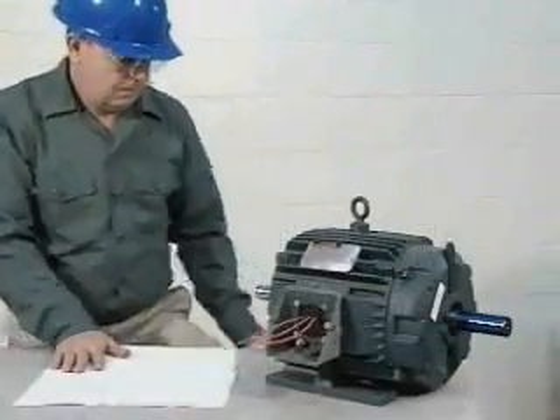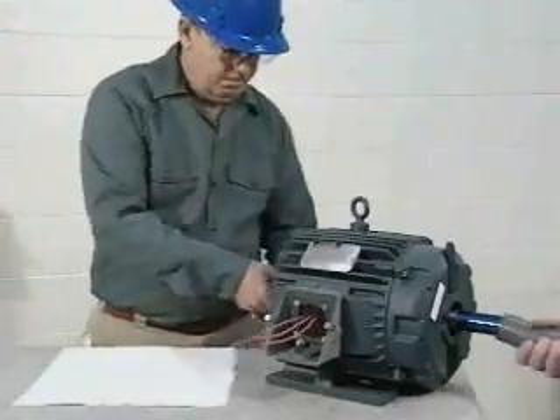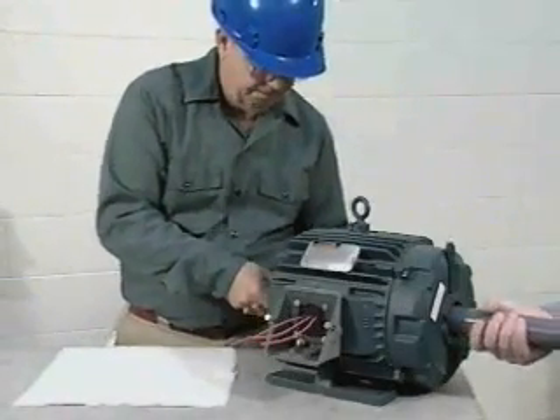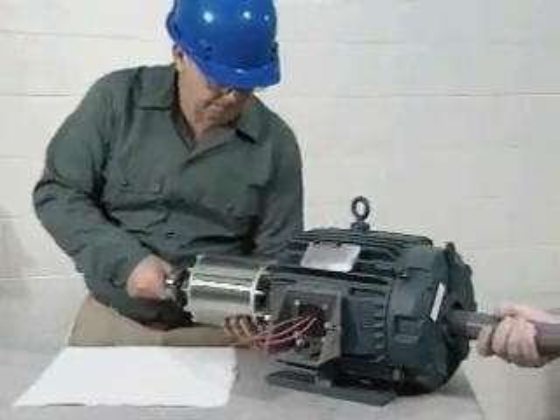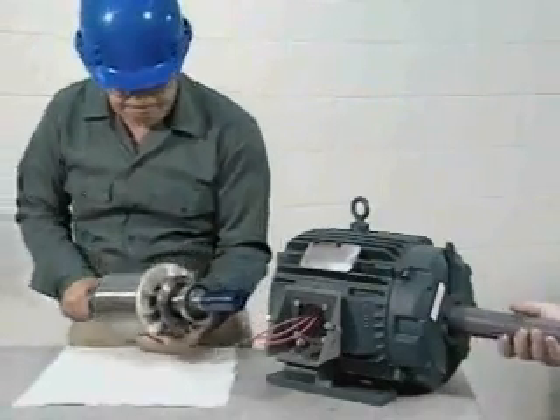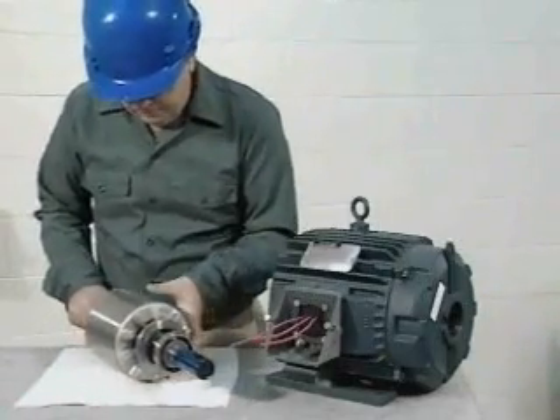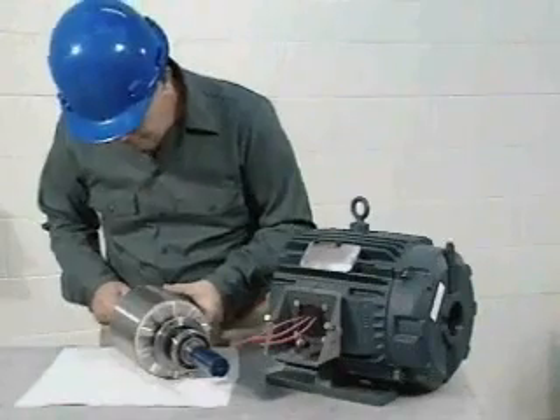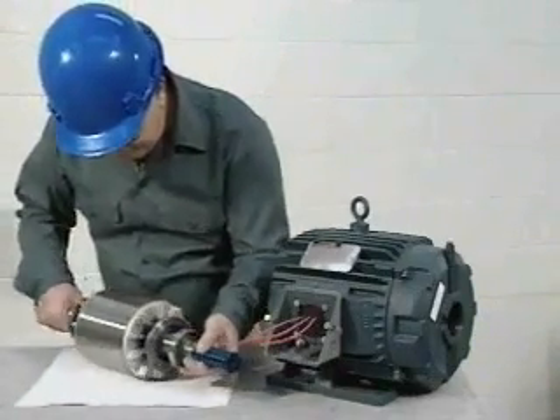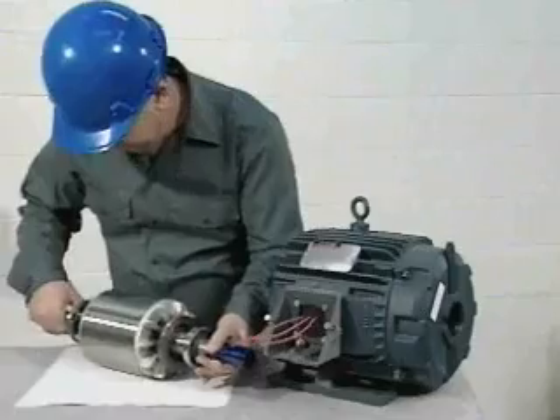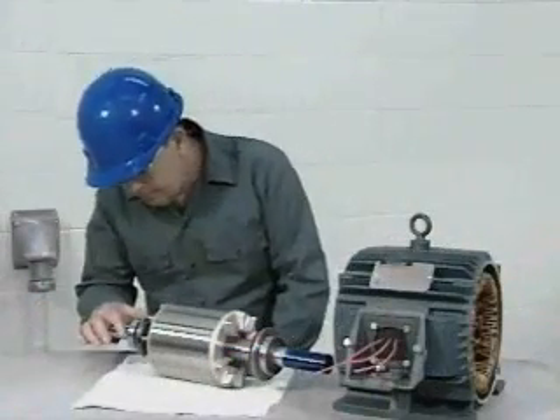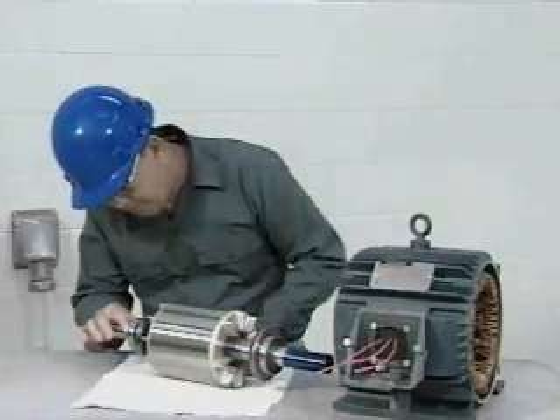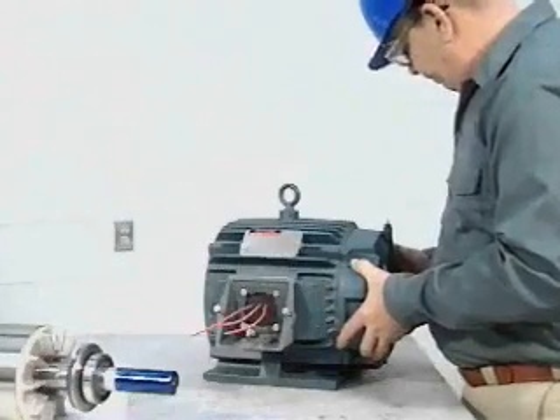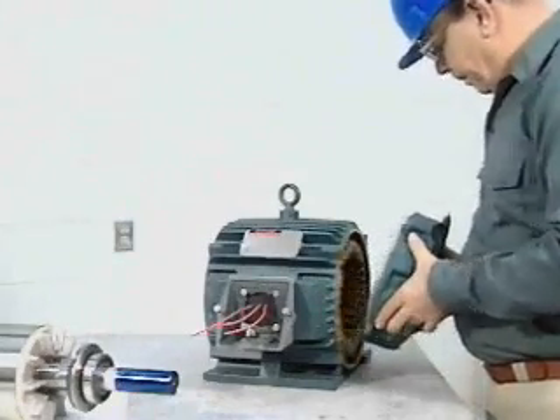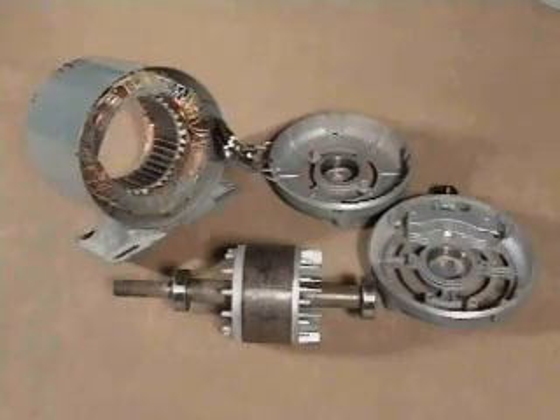Rotor removal is a very precise operation. It may take 2 people to do it. Make sure the clearance between the rotor and the stator is even on all sides and at both ends. The rotor must be properly aligned to prevent damage to the rotor or the stator windings as the rotor is removed. Set the rotor aside on a clean, soft surface where it will not be damaged or roll. Inspect the bearings according to the manufacturer's instructions. Replace the bearings as necessary. Remove the other end bell. Select Next to continue.